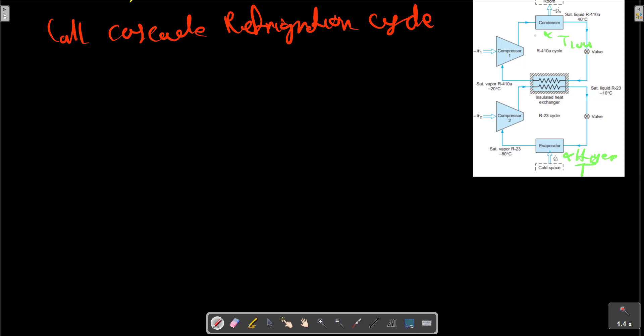The net effect is to lower the overall compressor work and increase the cooling capacity compared to a single cycle system, as shown in the figure here. Special low temperature refrigerant like R23 or hydrocarbon is needed to produce thermodynamic properties suitable for the temperature range, including viscosity and conductivity.